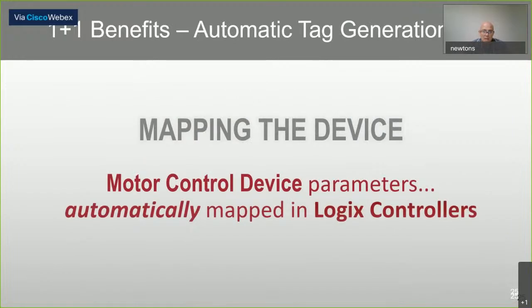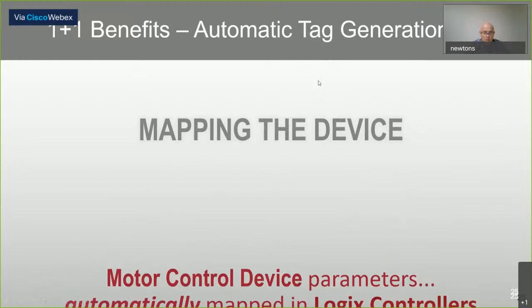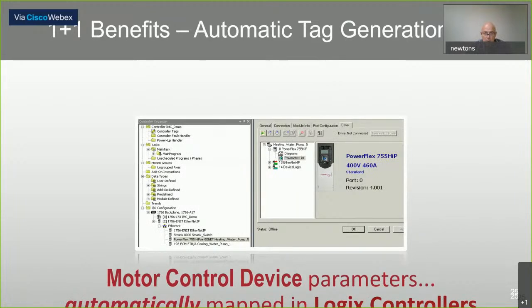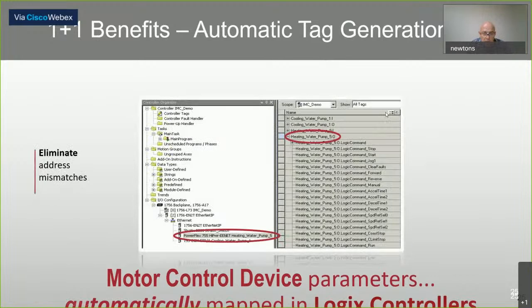So one of the first benefits is within the Studio 5000 software, and it's something we refer to as automatic tag generation, where we map a device into the tag database. As we see here over on the left pane, we've added a PowerFlex 755 drive into the project. We've named it heating water pump number 5, and simply on accepting that as an addition, on the right hand side in the tag database, we see pre-populated tags and subtags. And obviously you see there the naming convention is transferred over. The heating water pump 5 is there, and all the subset of tags is automatically added. So all the logic commands, the starts, the stops, forwards, etc., are all pre-configured for us.